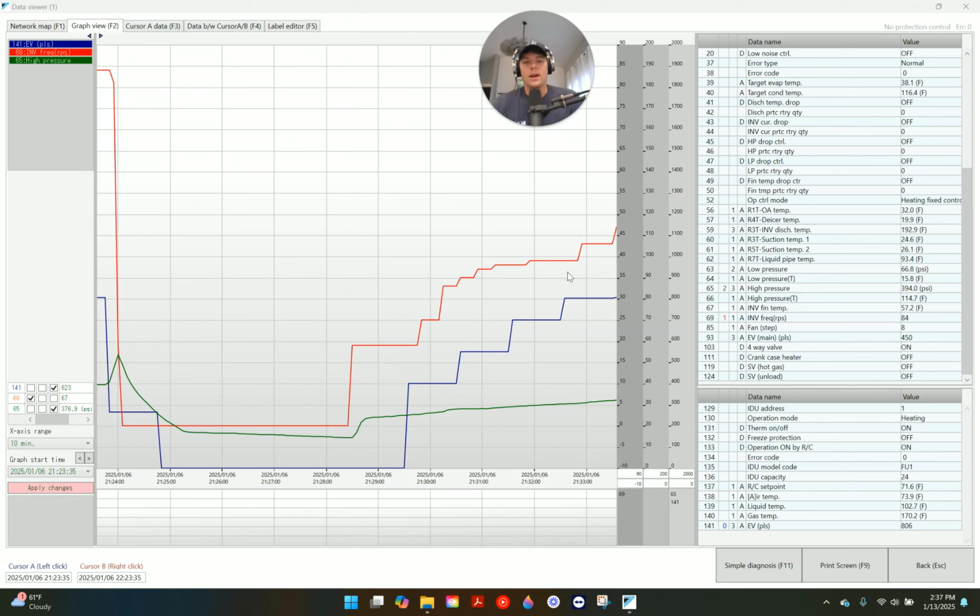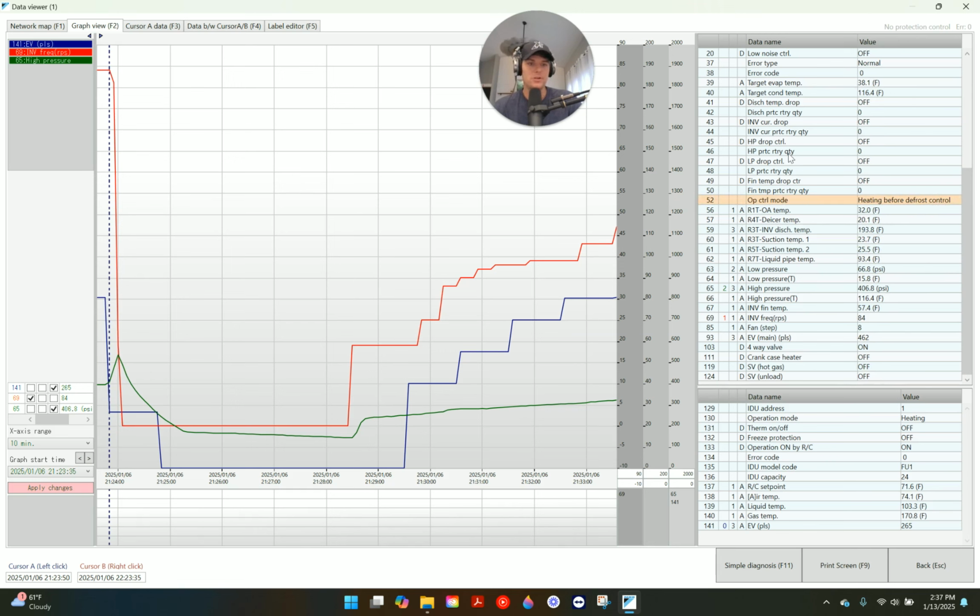So, all right, we know we've got the valve pulses, we have discharge pressure, we have compressor speed. Now let's walk our way through this data by clicking to see if anything jumps out at us. And I've already noticed there's a great thing here called operation control mode. I did a YouTube video on it. If you guys haven't seen it yet, there's an operation control mode in DChecker. Because remember, this is a Sky Air product, which is basically a VRV product. And it says right here, heating before defrost. Okay, what is heating before defrost?